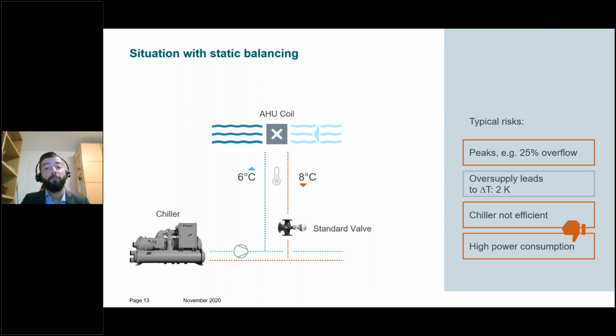And when the chiller pumps more energy into the system, if you have a standard valve which has no capability of compensating pressure fluctuations, then you likely end up having overflow during these moments in some places. But because the flow is distributed unevenly, the energy is not properly transmitted when you need it. So you're going to have excess overall energy, but somewhere the energy is lacking because there is too much of it somewhere else. This is what typically happens with static balancing.